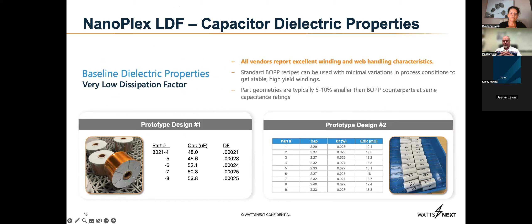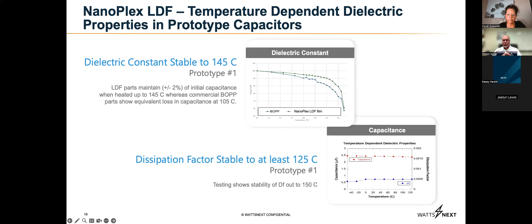And then, again, the properties that I described earlier, where the dielectric constant stays high as a function of temperature, that holds through in the devices that we're making. We're seeing the same sort of stability in the capacitance of the device up to about 145 degrees C. Whereas for the BOPP devices that we've characterized, these are commercial off-the-shelf devices, we're seeing the drop in capacitance happen at much lower temperatures. Additionally, you see the dissipation factor is stable out to about 150 degrees C. We have some new internal testing data. We've taken some devices up to about 150, 160 degrees C and compared them with polypropylene devices. Polypropylene devices typically see an increase in dissipation factor once you're out over 125 C, whereas our LDF film does not. Next slide.